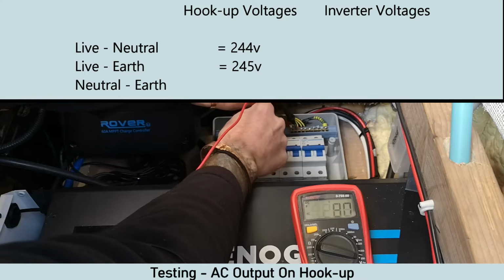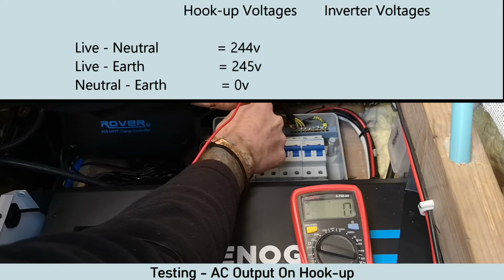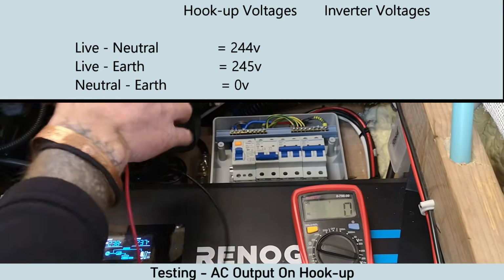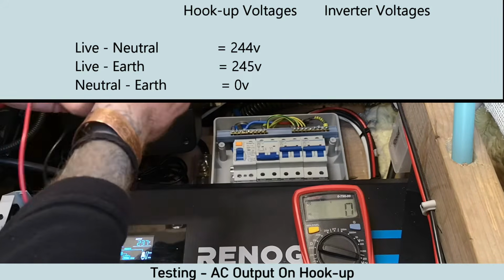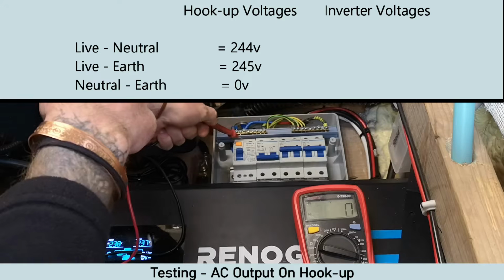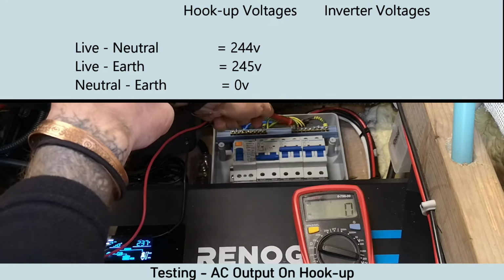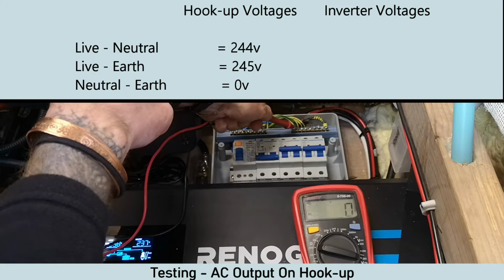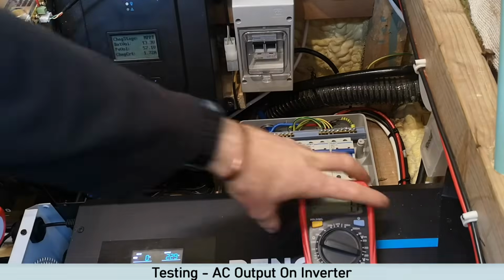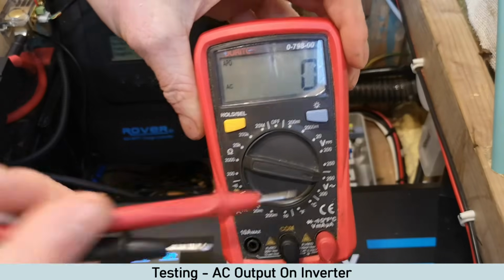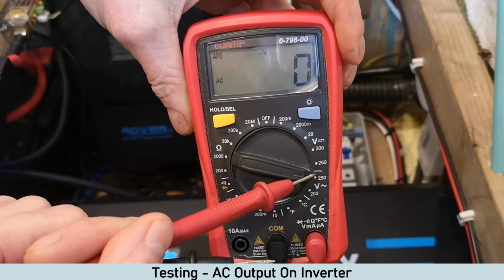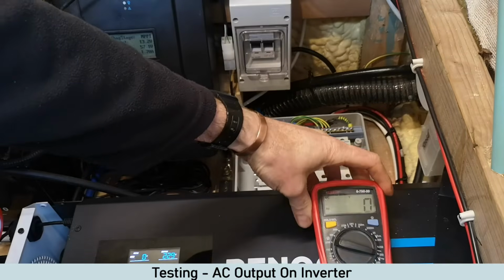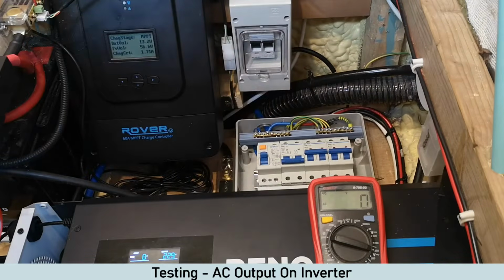If I go neutral to earth, I will get 0. The reason for that is the neutral and earth are combined at the source. So the live you've got 230, the neutral is 0 volts, and earth is 0 volts. Now the exact same test on the inverter: same tester, same setting, volts AC 250, because we're still getting AC voltage coming out. And then I'll do the same tests again.